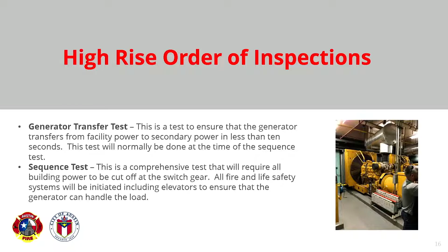The problem with sequence test rescheduling is that everybody has to be there. Electrical, mechanical, controls, generator tech, electrician, general contractors, alarm contractors, sprinkler contractors. We have to get everybody there all at one time and hopefully not interfere with your job site too much. We will typically schedule them later in the afternoon so you can give the rest of the job site the day off after lunch, because we're going to kill power at the switchgear to the building.